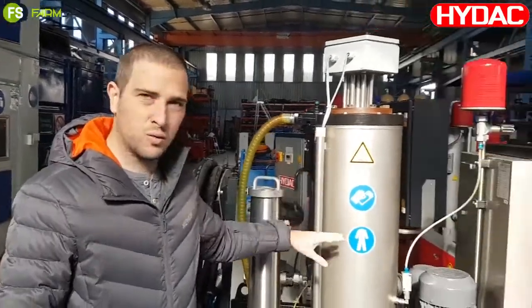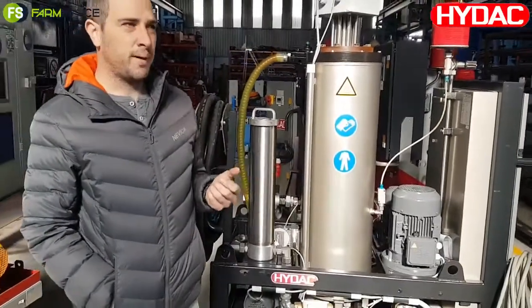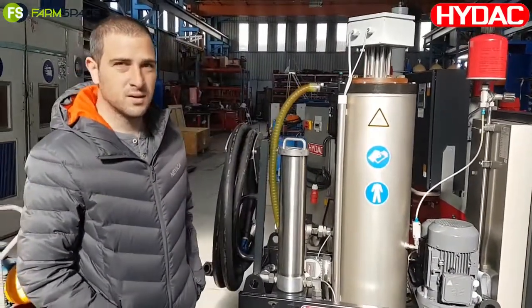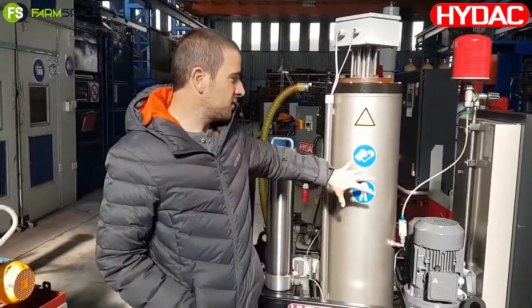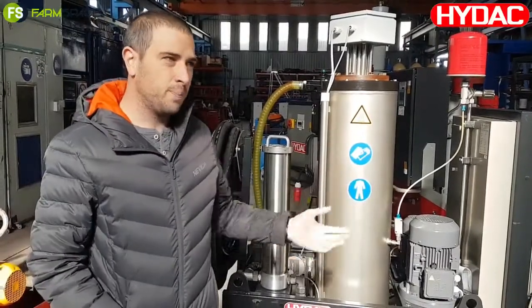So what we do now is we condition the oil through taking the water out, as well as it goes through a filtration system to condition the oil back to the right cleanliness class and quality that you need to prolong the life of your system. Does it make financial sense? Yes. Look, this is expensive equipment, so we rent these out to clients. We do sell them, but in most applications, if you rent it for a week, it can bring your oil back down to a cleanliness class that you need, and that will prolong the life of your pumps and your hydraulic valves.